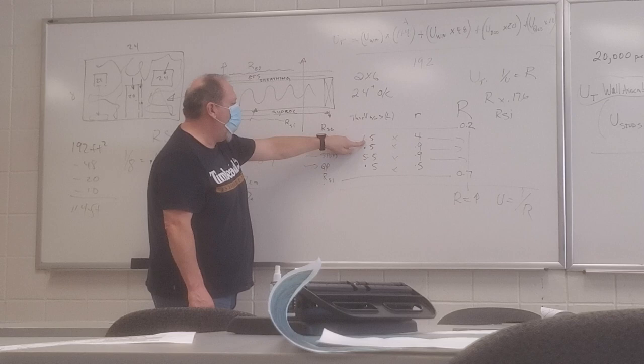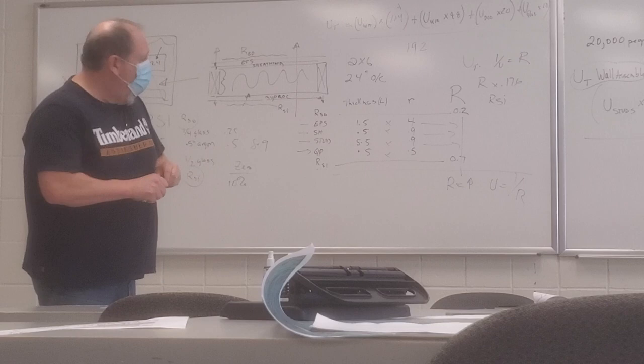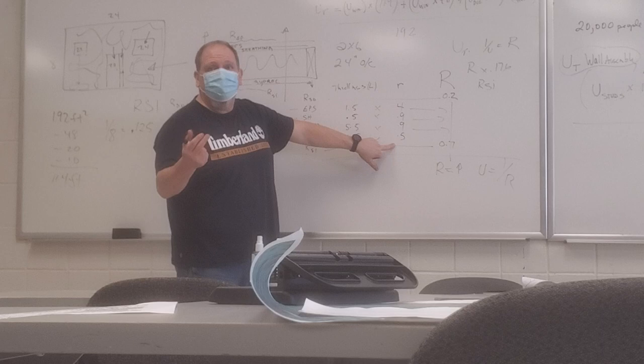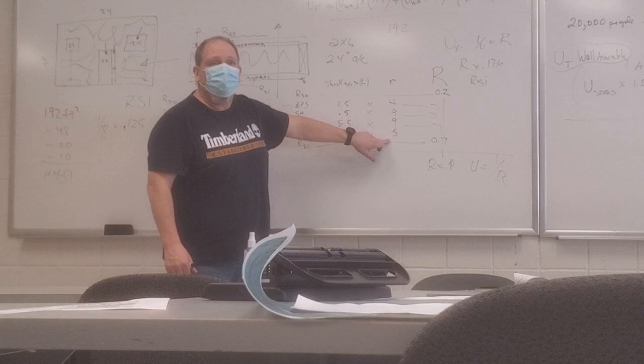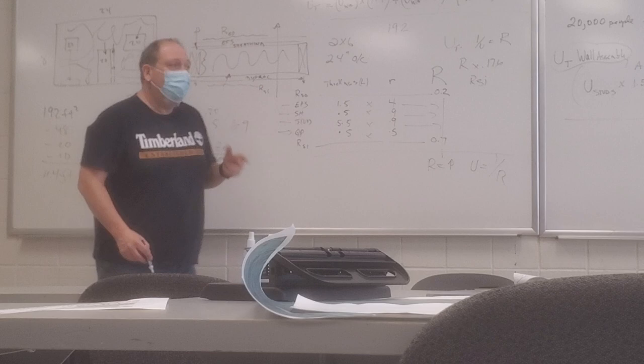EPS was... So you do that same thing? Yes. So you do the exact same thing, but just switch of stud insulation. So then you go into that chart, and you guys got it. It's in your notes. So I said, have it all ready. You've got to look up the resistivity or a rho-value, which is based on the density. You look that up, and then you multiply that out, and it gives you an R-value of that component, and then you add them all up.